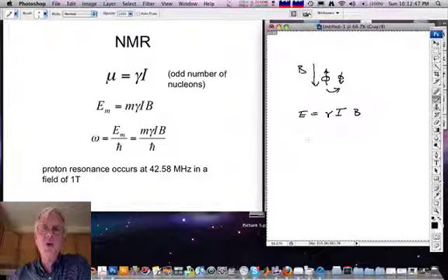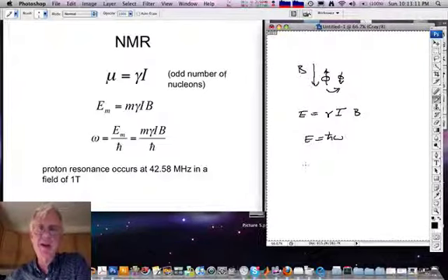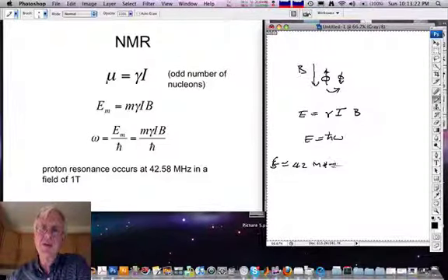So in water, using E equals h bar omega, we can calculate a frequency with which radiation would have to be shone on the mixture of protons in a given magnetic field to flip their spin from one direction to another. The result is to achieve a slight surplus over a Boltzmann distribution of spins in the high energy state. Well, it turns out for a proton in water that the resonant frequency is roundabout 42 megahertz for a field of 1 Tesla.